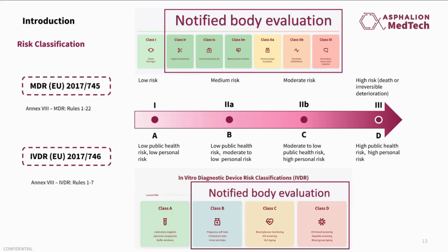The most important thing about the risk classification is that, as I said, it will define the applicable conformity assessment process. So for class 2A, class 2B, and class 3 devices, and also class 1 devices that are intended to be reusable, sterile, or with a measuring function, these devices will need the involvement of a third party, which is called the notified body, for obtaining the CE mark. In the case of class 1, they can be self-certified directly by the manufacturer. The same applies for the IVDs, but in this case, the notified bodies are required for those classified as class B, class C, or class D. Those devices that are class A can be certified by the manufacturer itself.